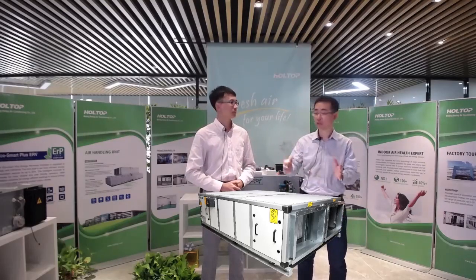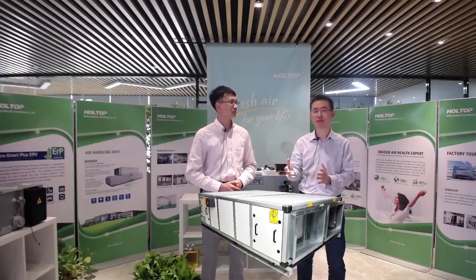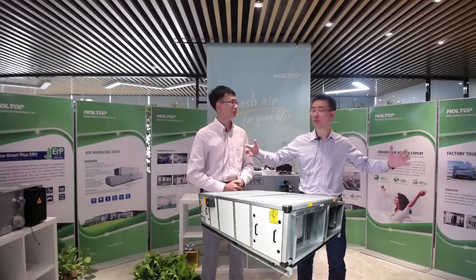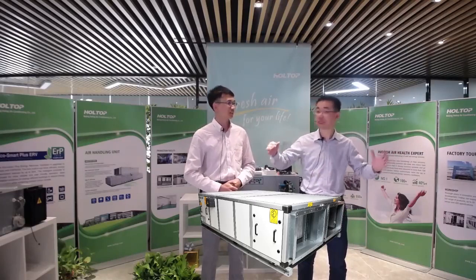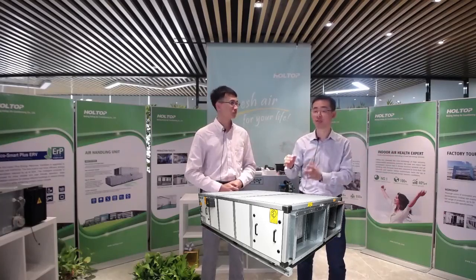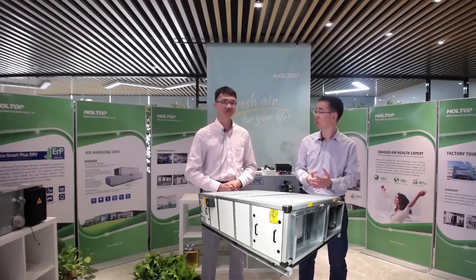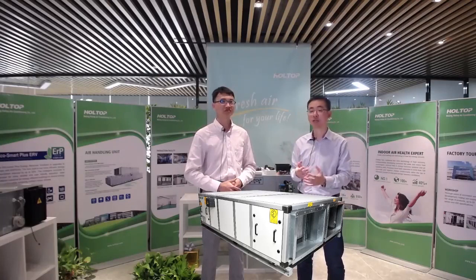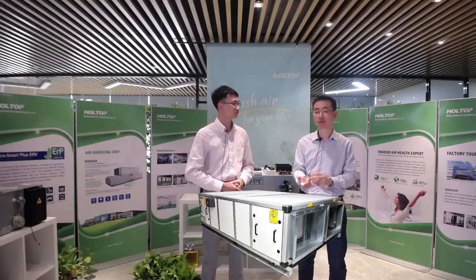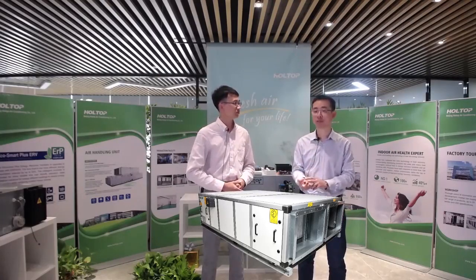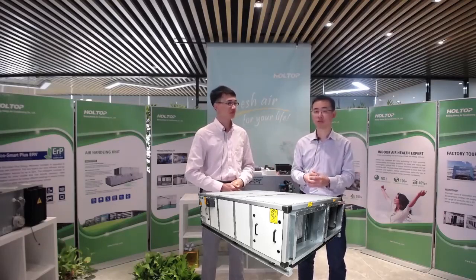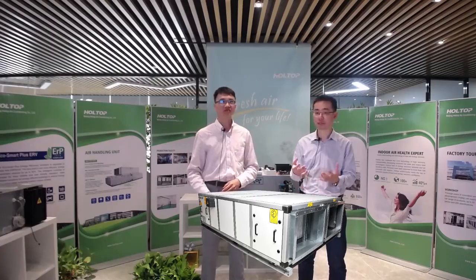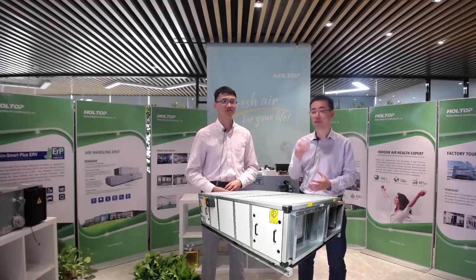And what's more, because some of the offices have very long ducting to distribute air to each corner of the room, there is a request for high external static pressure. Our units can be 100, 150, 250, and 300 Pa to meet the requirement. So our unit is a very good solution for the class office.